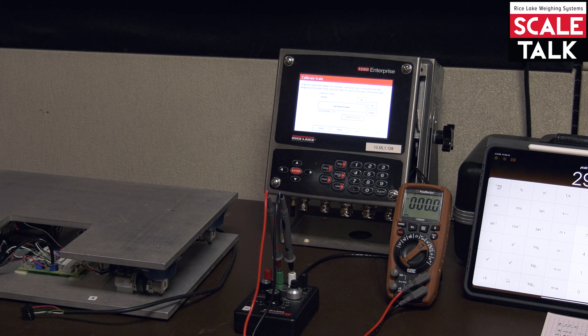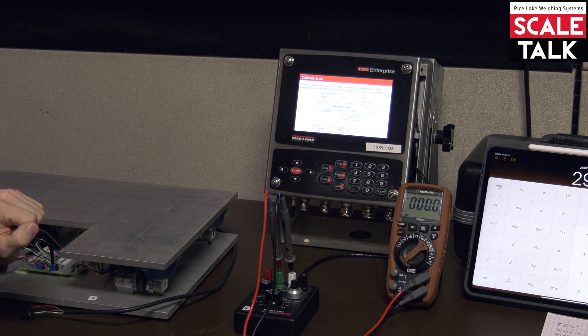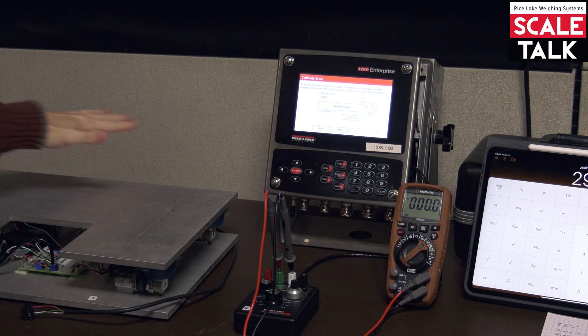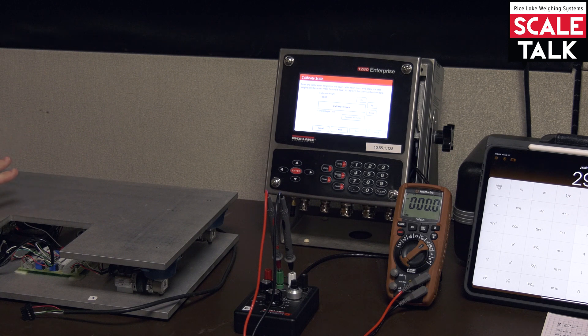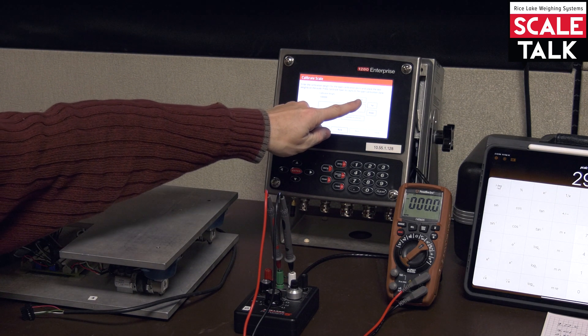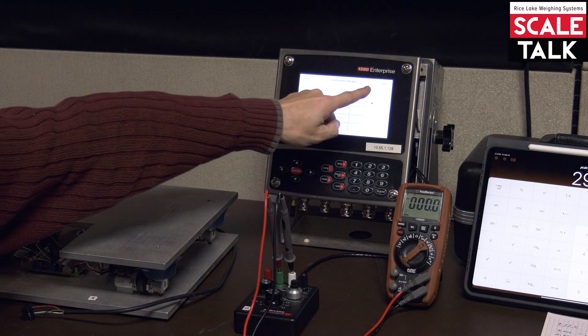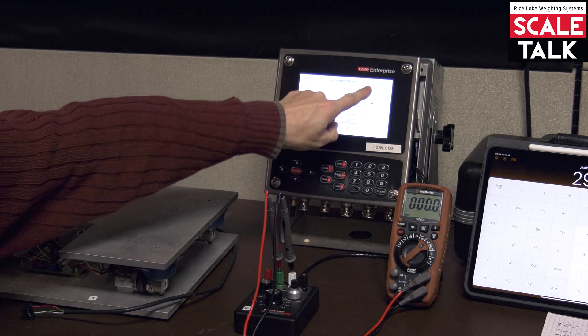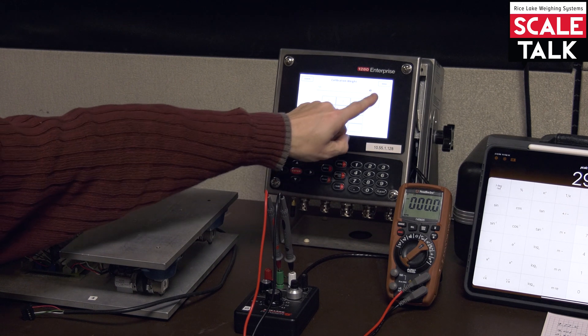And for our span remember this is a 50 pound scale. Even though we have a hundred pounds of build due to the four 25 pound load cells it's a 50 pound scale. That's how we're configuring this scale to be. So when we do our span calibration we're going to set that weight value to be 50 pounds. So we'll enter 50 pounds here.